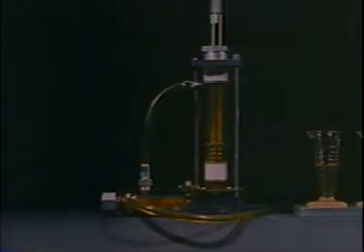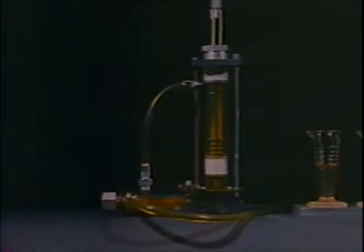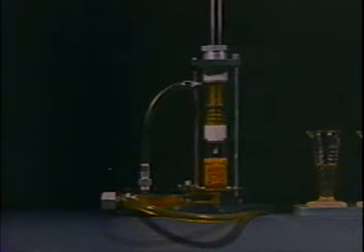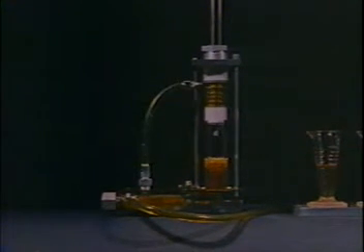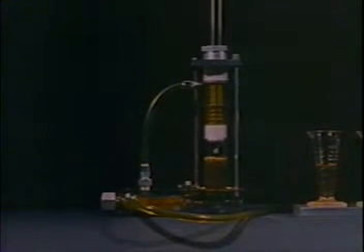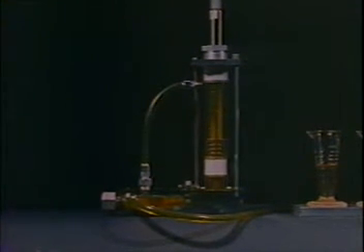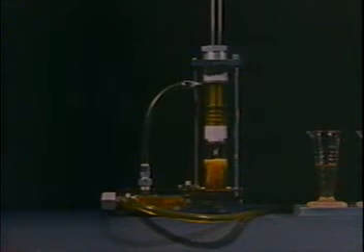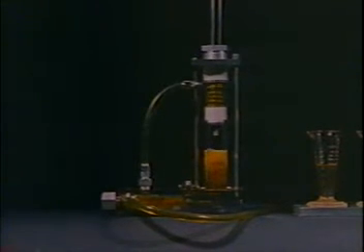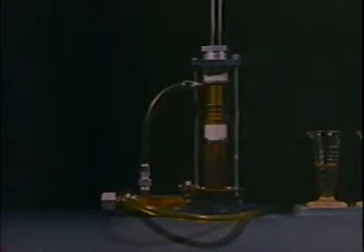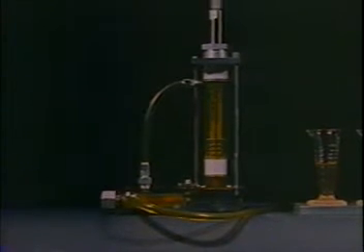Another way in which the pump can be incompletely filled results from lack of incoming flow, causing the piston to rise faster than the liquid level. This is called cavitation, describing the cavity or void which develops below the piston.